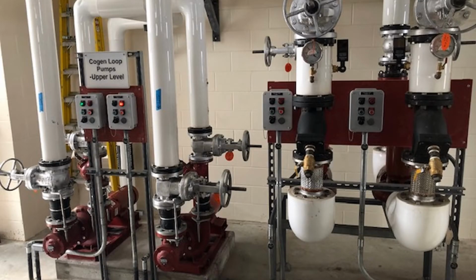There are a series of pumps needed to move all of this hot water around. There are pumps that go out to our cogen units to extract heat off the engines. We've got pumps that are circulating through the boiler system. There are pumps that send hot water through the heat exchangers, as well as supplying a handful of air handler units for the digester equipment building itself.